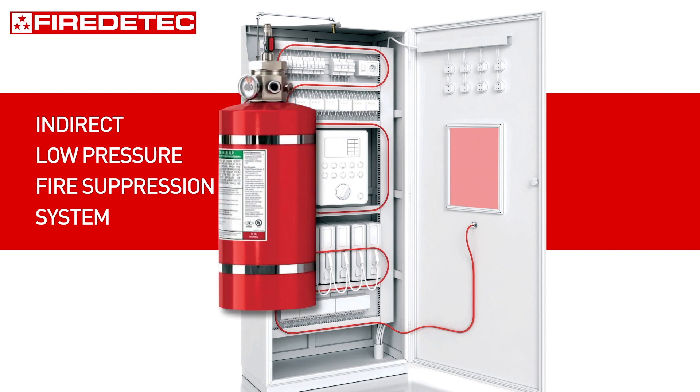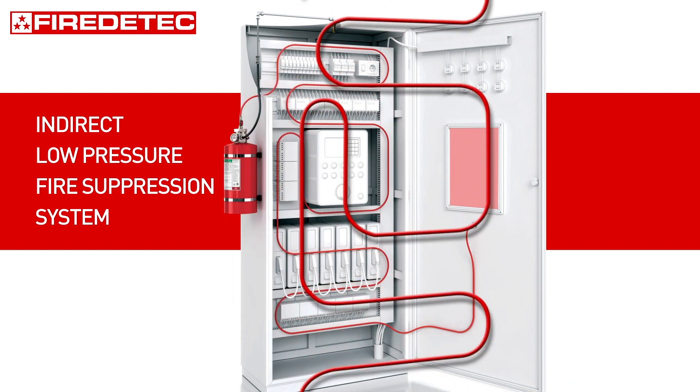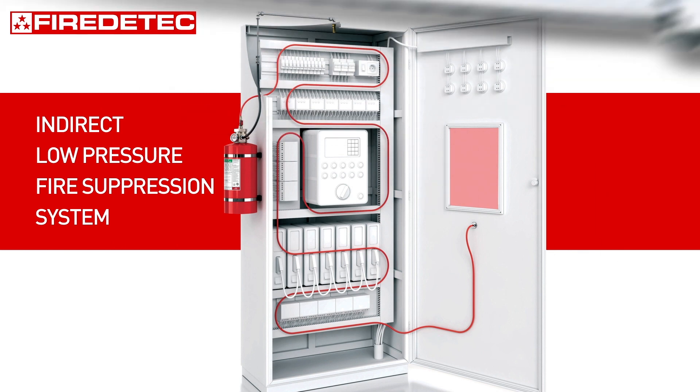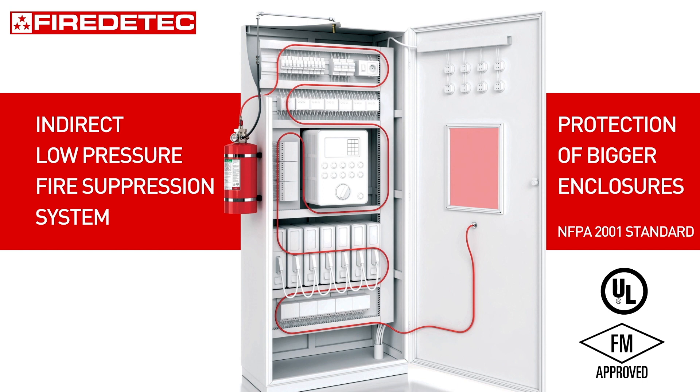The indirect low pressure FireDetec system consists of a cylinder filled with Novec 1230 fluid, a pneumatic detection tube pressurized with 16 bar nitrogen, and a discharge line with 1 to 2 nozzles. The FireDetec indirect low pressure system is UL/FM approved and designed according to NFPA 2001 to protect bigger enclosures.